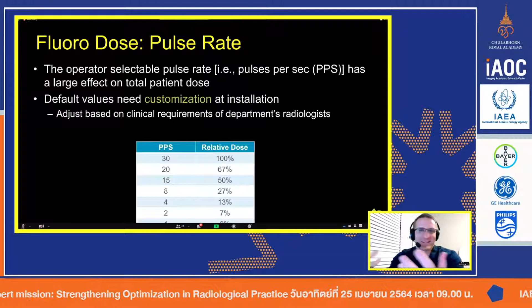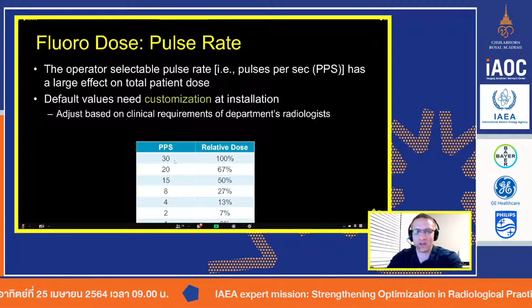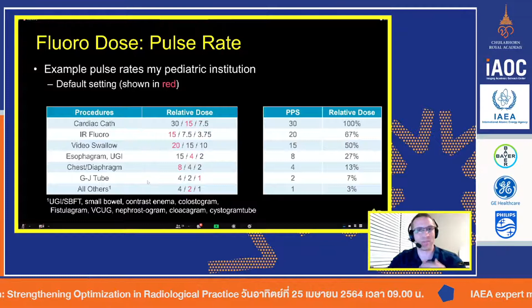Now, we've had other people come in and they've said to themselves and to us, 1 pulse per second is too slow. Obviously, at 1 pulse per second, you're getting 1 image per second. So you have to adjust the way you think. You can't just go in and stick that tube and go right over into your patient, because obviously you're moving faster than 1 frame per second. And so it does take a paradigm shift on how you operate the machine. If you're willing to do that, and if you have the comfort level, then you can probably pick most pulses per second depending on the type of procedure you're using. This is simply an example. Once again, this is how we do it at my center. I'm not saying this is the right way.